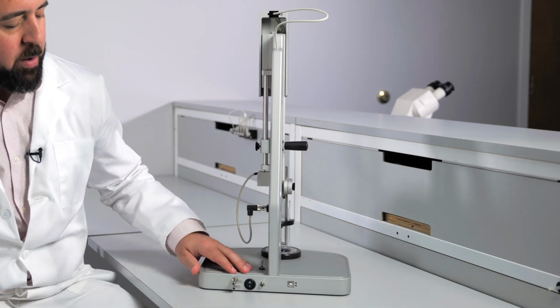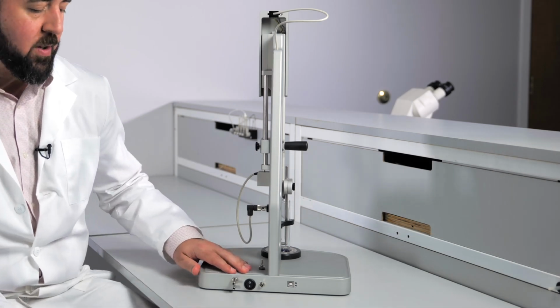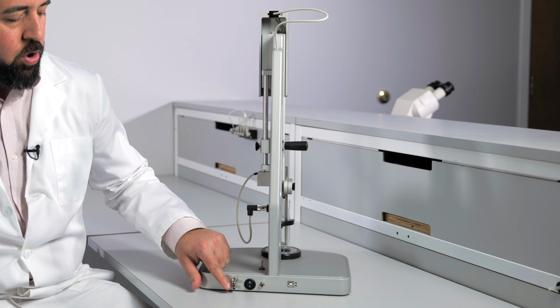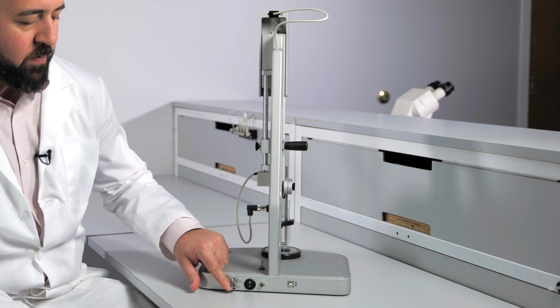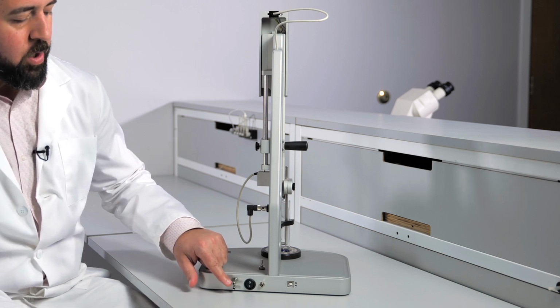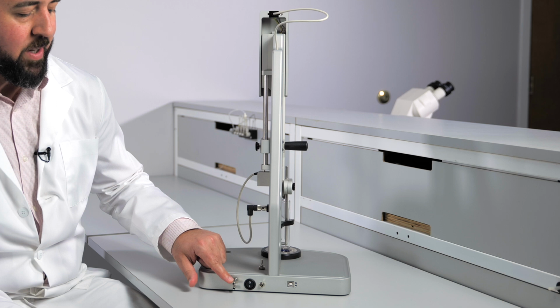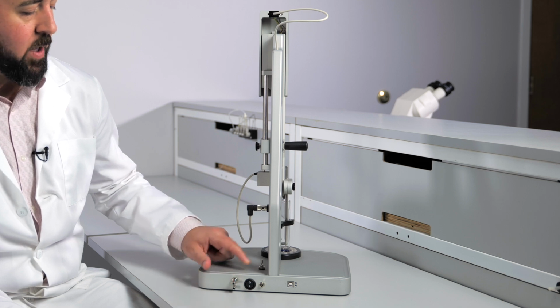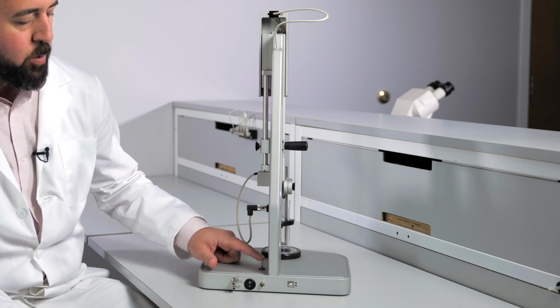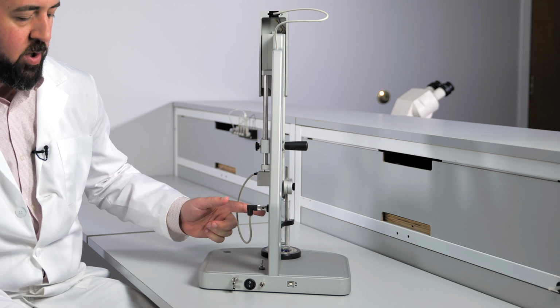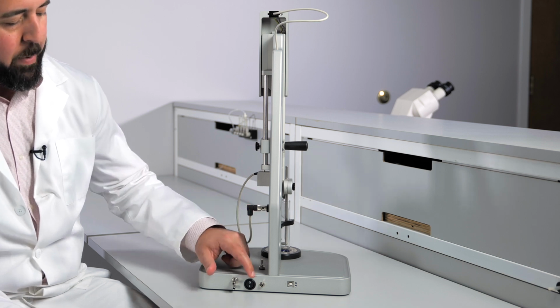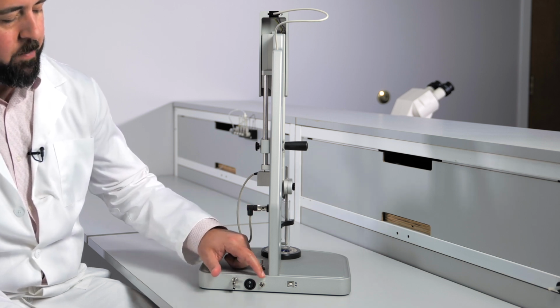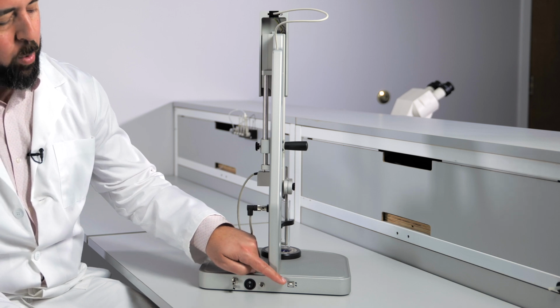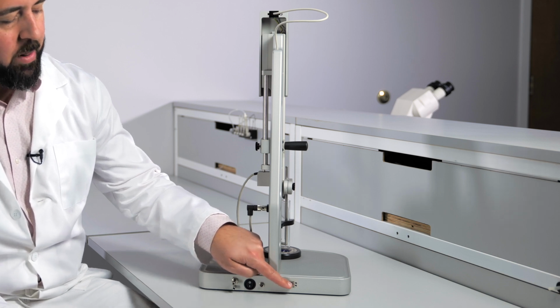The connections on the back of the puller allow you to fully utilize the system. You have a connection which will go to the vacuum source. You have a port for a gas line that will come from your gas tank, as well as a needle valve which will control the amount of bubbling in your tissue chamber. You have a power switch and a power supply. You also have a port for a USB cable and lights showing data communication.